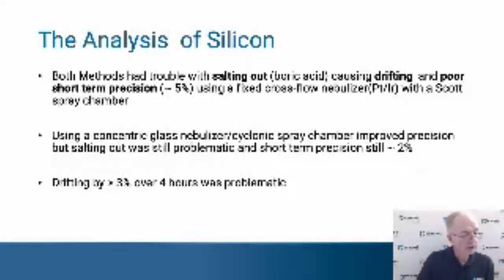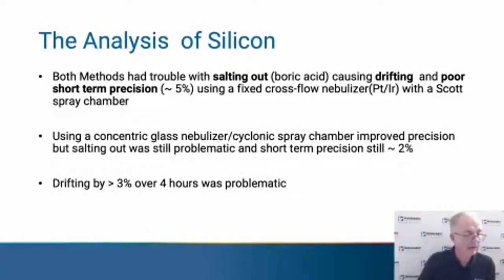Now, we were using a concentric glass nebulizer and a cyclonic spray chamber at this time, and that combination did improve the precision somewhat, but it was still around 2%, which was not good. And then on top of it, the system tended to drift. Again, we ascribe this to the salting out effect.